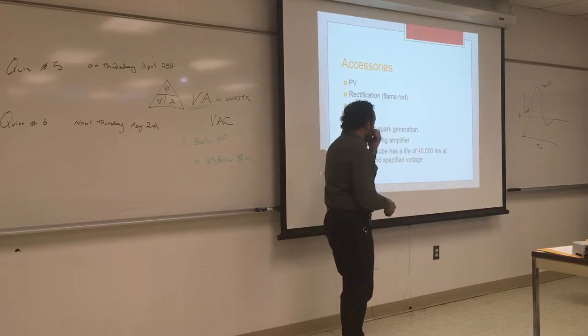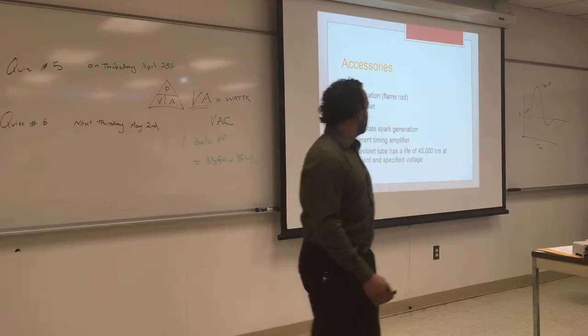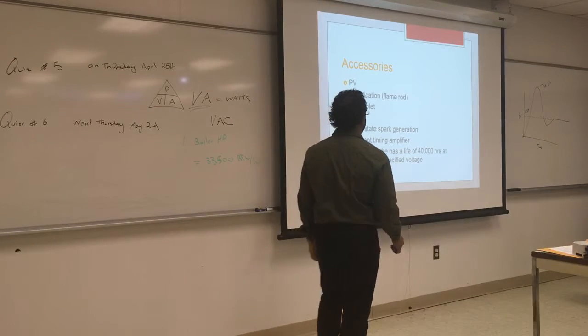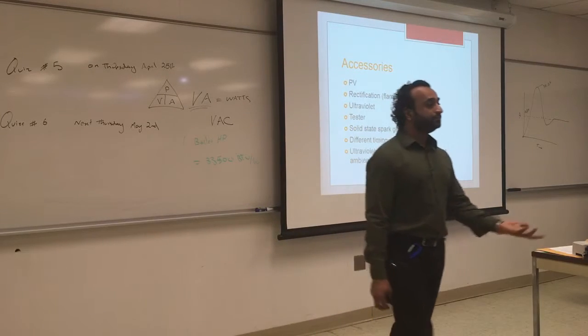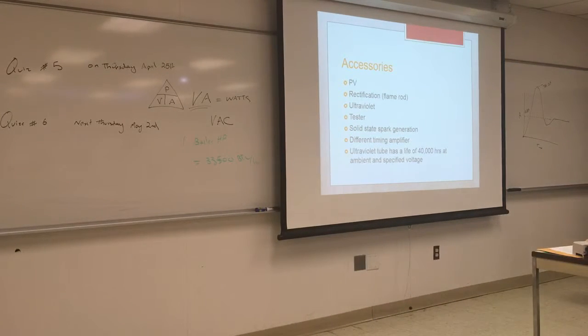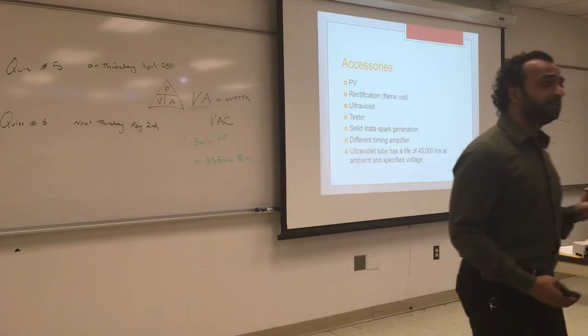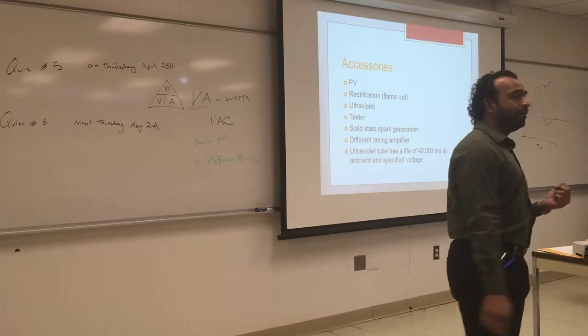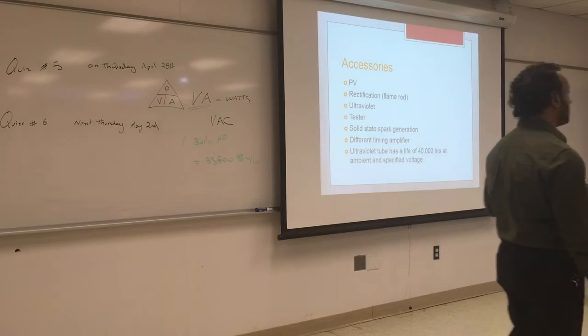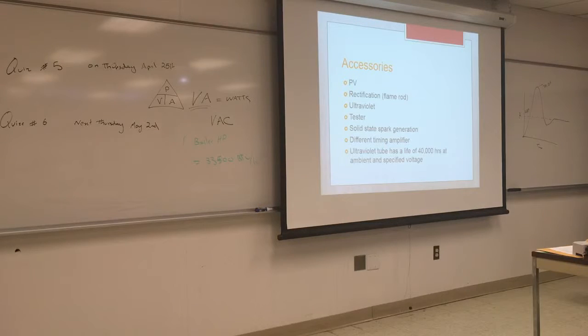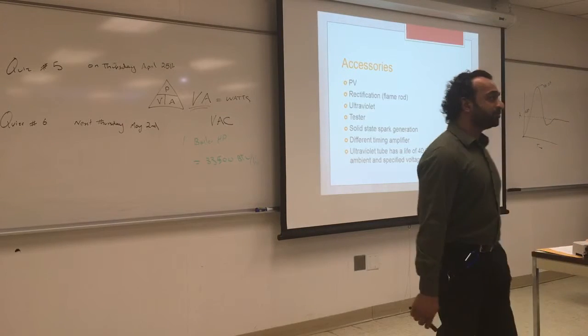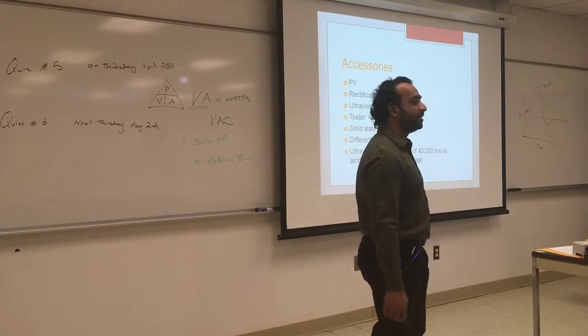The ultraviolet tube has a life of 40,000 hours at ambient temperature and specific voltage. Those ultraviolet cells always deteriorate with time. Over time, they die out. It's like the solar panels in your house, they have a life expectancy. I think it used to be 15 years, now it's 30 years. But most of these things deteriorate and lose efficiency over time. So this is the expectancy of how long it will last. 40,000 hours, so this should be a record of how many hours this boiler is running and when the ultraviolet is expected to fail.